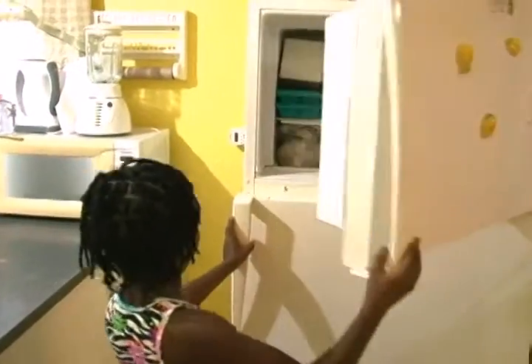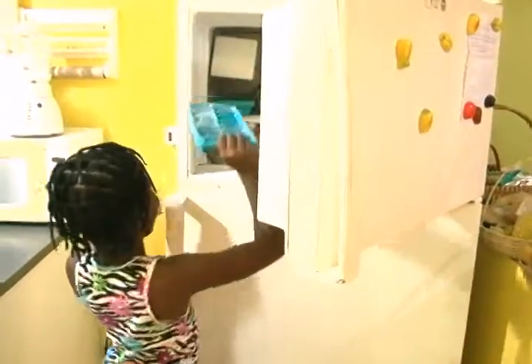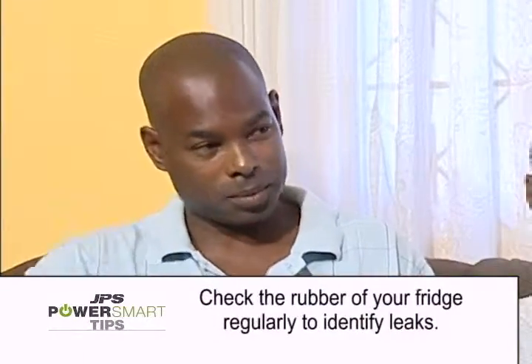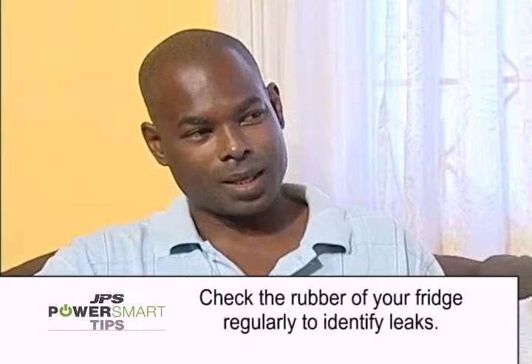So they have been cooperative, and we do speak a lot, and we do a number of visits since the first shoot. We did an internal audit, and one of our biggest consumers was our refrigerator. There were some leaks at the bottom of the doors that were unnoticeable. So that's why you weren't seeing any change, although you had a timer on it. And also that refrigerator has two compressors, one for the freezer section and one for the lower section, which is the cooling section.